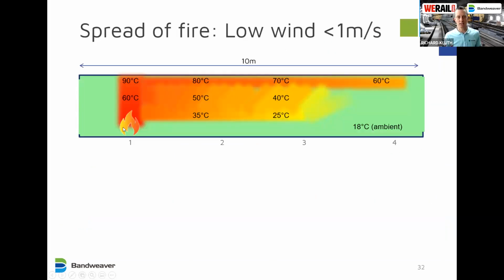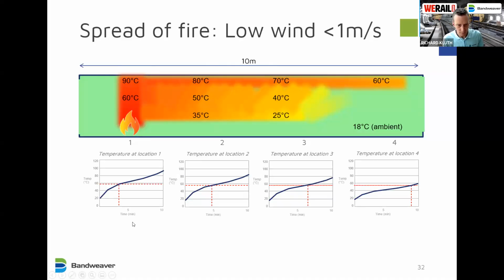So if we look at a fire in a low wind speed tunnel, we look at a 10-meter section of tunnel. It behaves more or less as you would expect. You have the fire, the heat is hottest directly above the fire, it's hottest at the ceiling level, and it reduces the further away from the fire you go. If we look at each of these points, 1, 2, 3, 4, and how the temperature develops over time, you can see it steadily rising, a little bit less as you get further away from the fire.